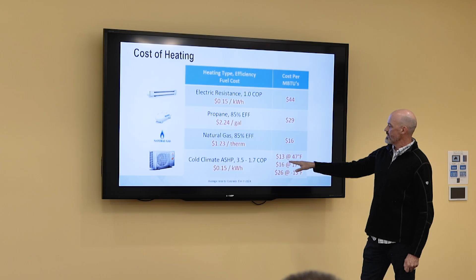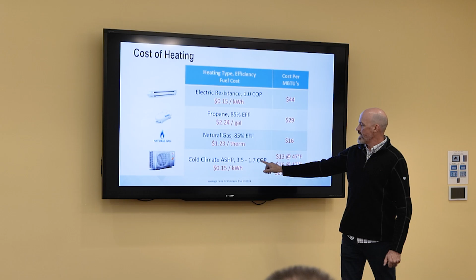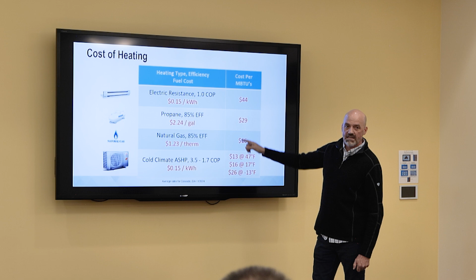Heat pumps are a different animal. It depends on the efficiency at what temperature. We're very efficient, beating everything when it's moderate temperature outside. We're roughly a wash at 17 degrees in these scenarios, estimating somewhere between a 3.5 COP and 1.7 COP. The 1.7 COP, when it's cold outside, is closer to propane in cost, more expensive. So that's when you start to think about what your backup fuel energy source is, and how to supplement when it's really cold outside, thinking about those costs.